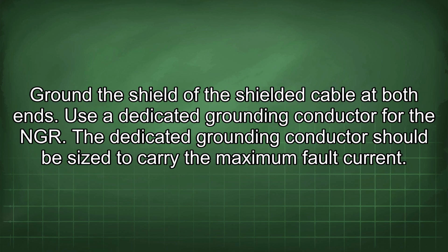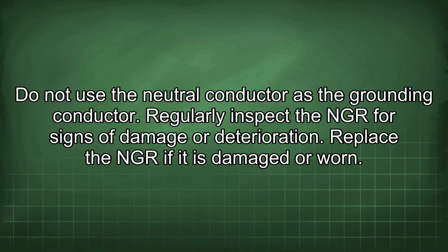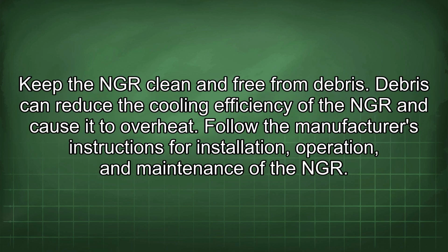Ground the shield of the shielded cable at both ends. Use a dedicated grounding conductor for the NGR. The dedicated grounding conductor should be sized to carry the maximum fault current. Do not use the neutral conductor as the grounding conductor. Regularly inspect the NGR for signs of damage or deterioration. Replace the NGR if it is damaged or worn. Keep the NGR clean and free from debris. Debris can reduce the cooling efficiency of the NGR and cause it to overheat.